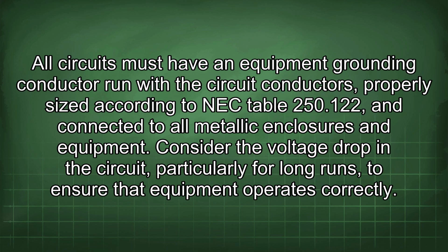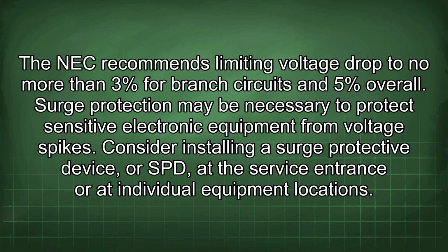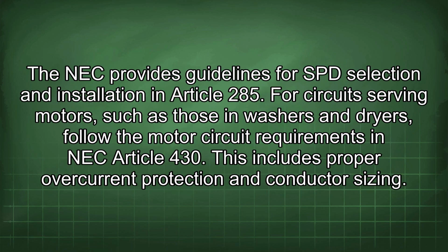Consider the voltage drop in the circuit, particularly for long runs, to ensure that equipment operates correctly. The NEC recommends limiting voltage drop to no more than 3% for branch circuits and 5% overall. Surge protection may be necessary to protect sensitive electronic equipment from voltage spikes. Consider installing a surge protective device, or SPD, at the service entrance or at individual equipment locations. The NEC provides guidelines for SPD selection and installation in Article 285.